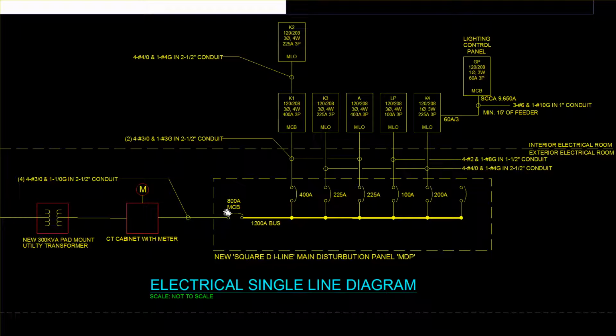Actually, if you look in the code, a service is allowed to have 6 switches, 6 handles, which is often called the 6-handle rule. We could have foregone this 800 amp main and then just used these 6 as our distribution, but we wanted the ability to add loads in the future. And so this panel board actually has room for quite a few more breakers. And so that's what we've done, we've put a main on this so that we wouldn't be hindered later on.